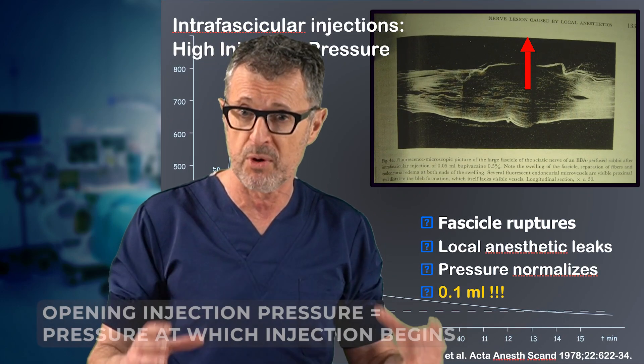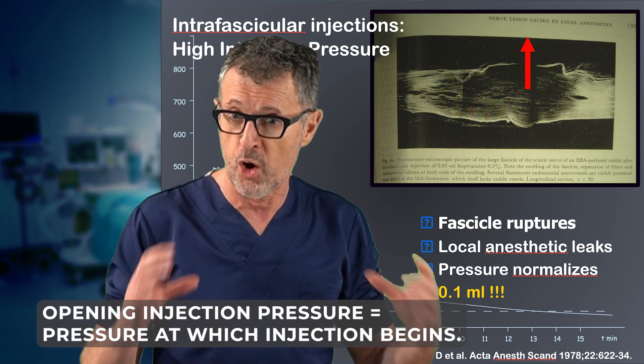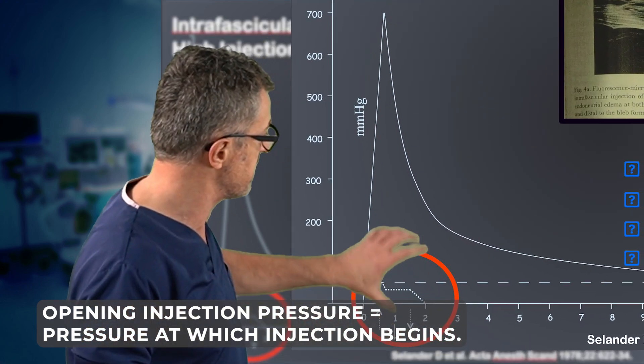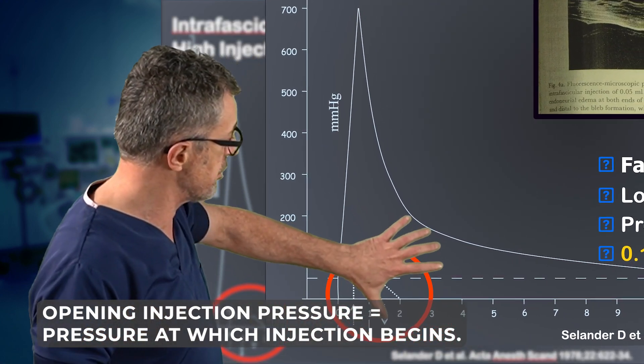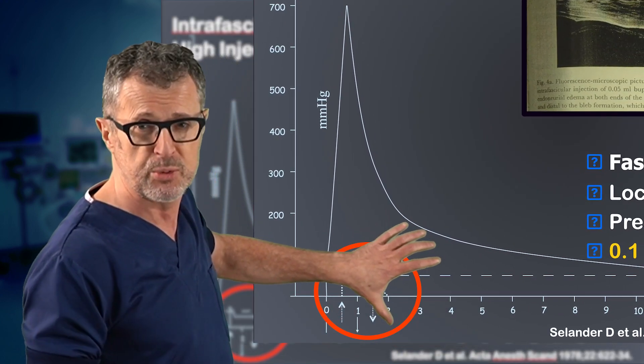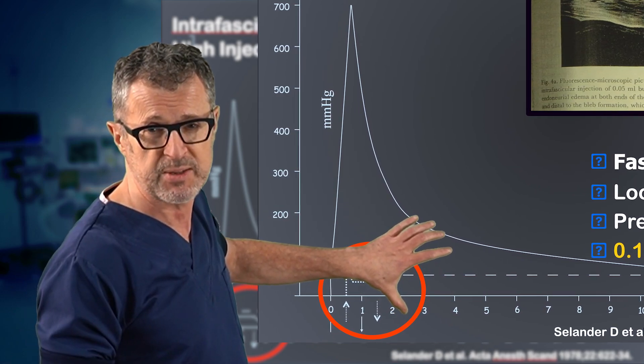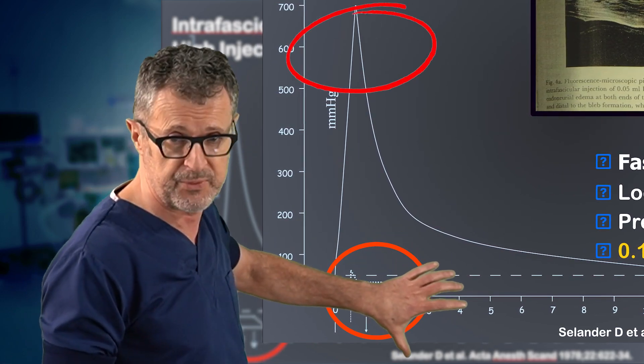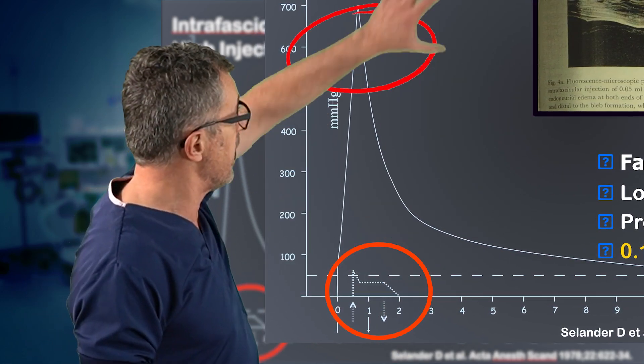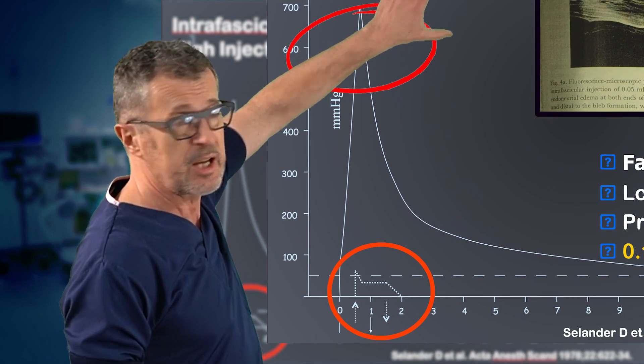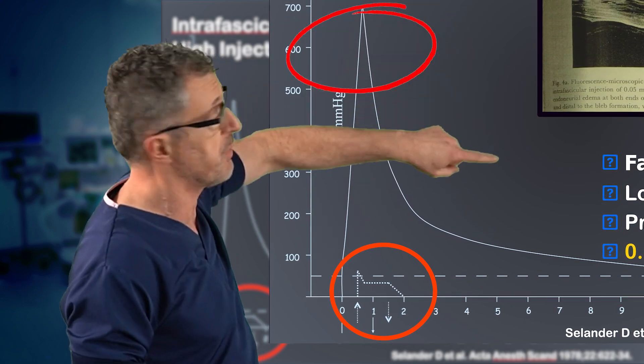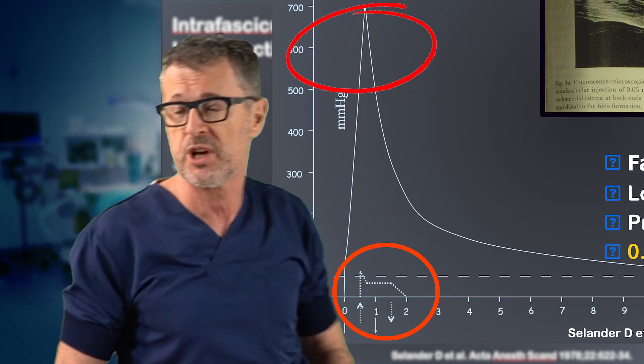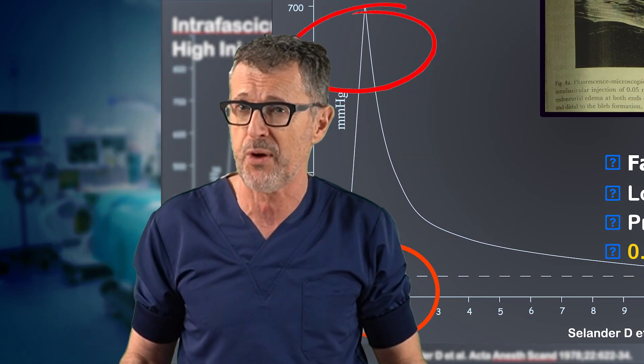We monitor the opening injection pressure. Here you can see that the injection pressure during injection around the fascicle or outside of the nerve is very low, and that the opening injection pressure is very high once you inject into the fascicle.